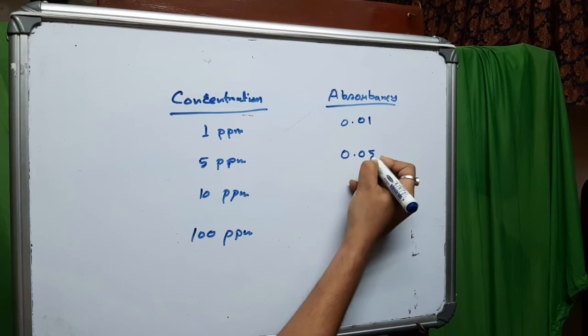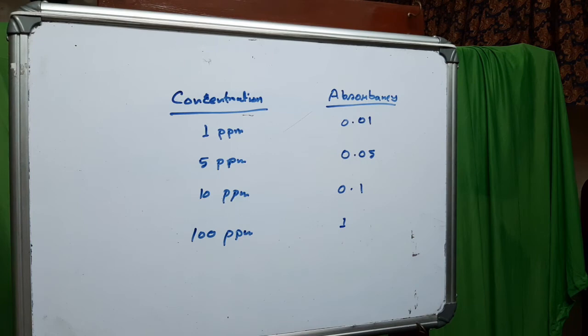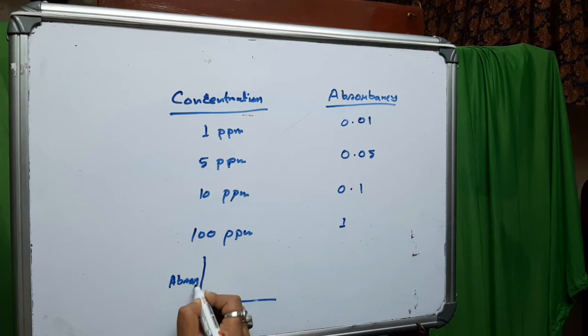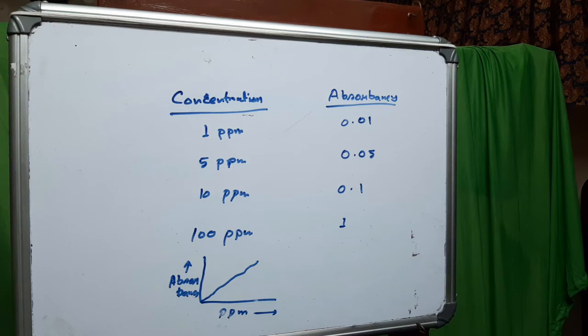For example: 1 ppm gives absorbance 0.01, 5 ppm gives 0.05, 10 ppm gives 0.1, and 100 ppm gives 1. Then make a graph of ppm versus absorbance. This graph goes through the origin because at concentration 0 the absorbance is 0. This relationship is called the calibration curve.